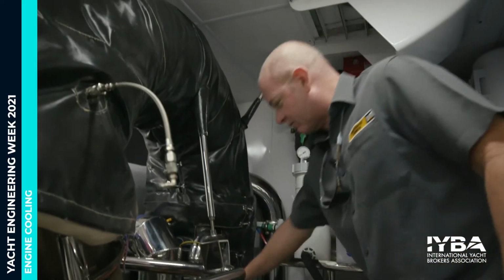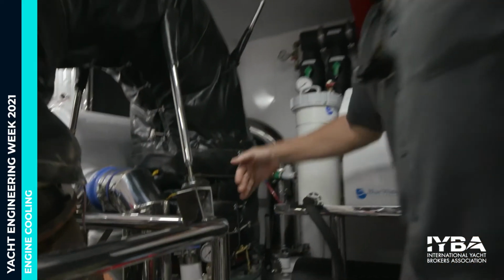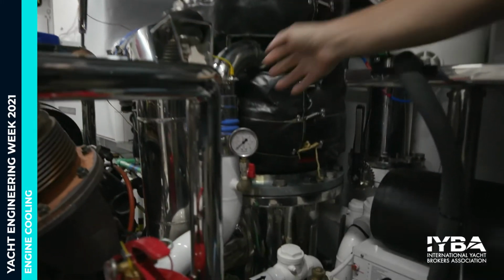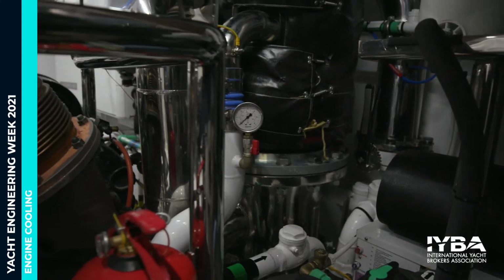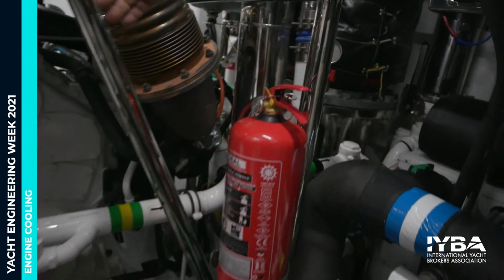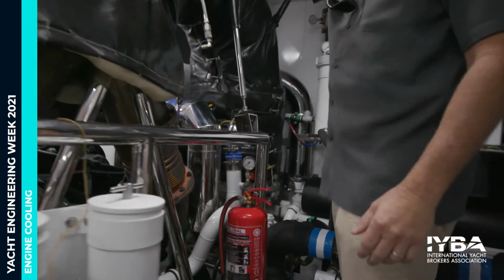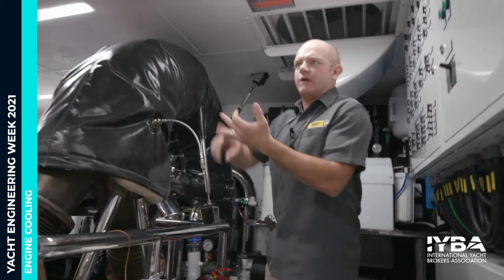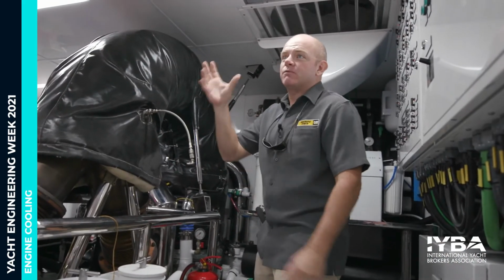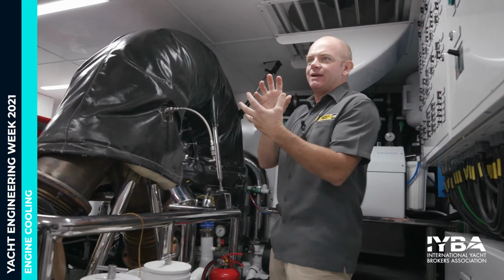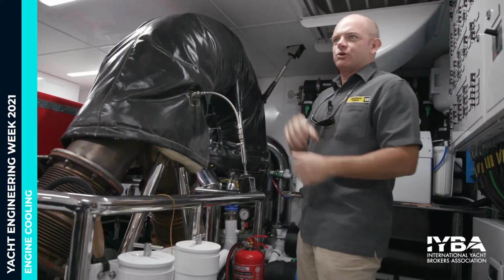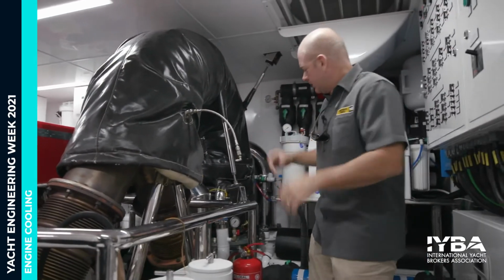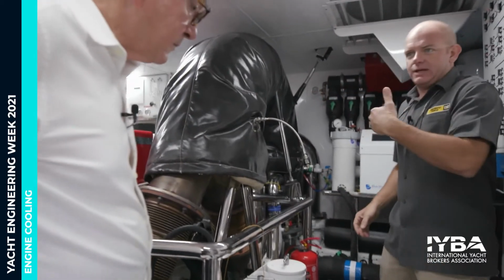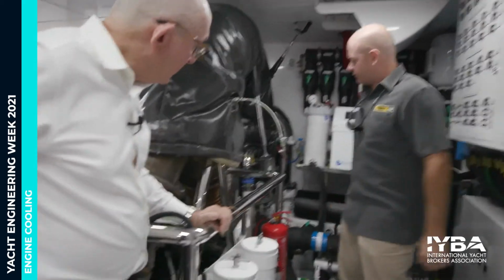Pressure gauges let you see if you get a restriction here, which would tell you there might be a restriction, possibly as far back as the transmission cooler, which often gets overlooked, or forward up to the heat exchanger or aftercooler. Your pump impeller blades may be starting to get old, they get a little memory to them, and they don't pump quite as much as they used to. Having something like that at the end of the system that you can monitor is a huge help.